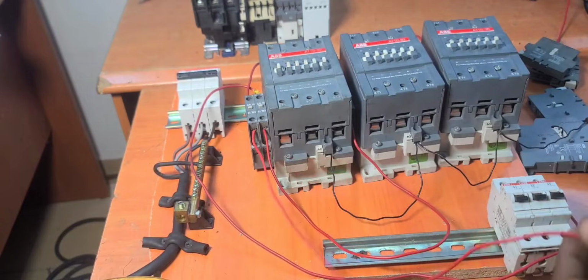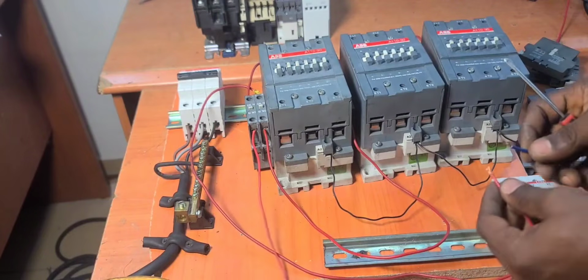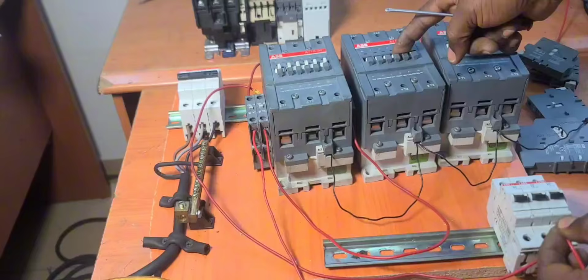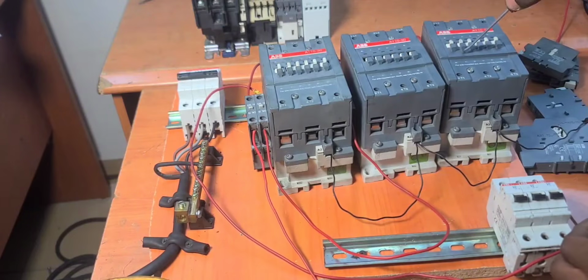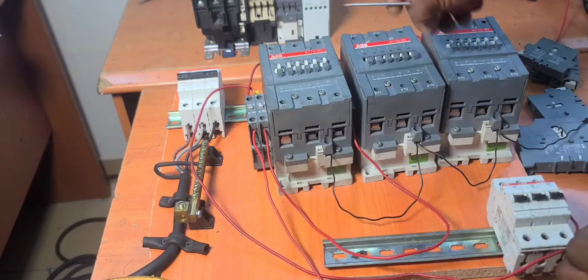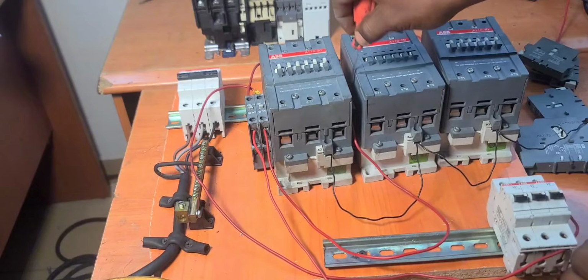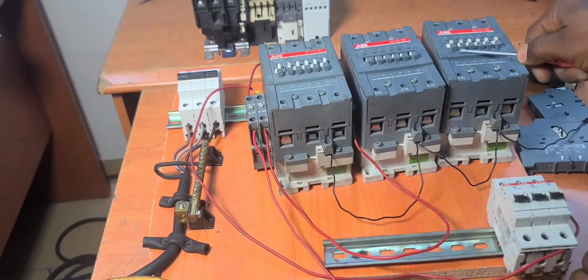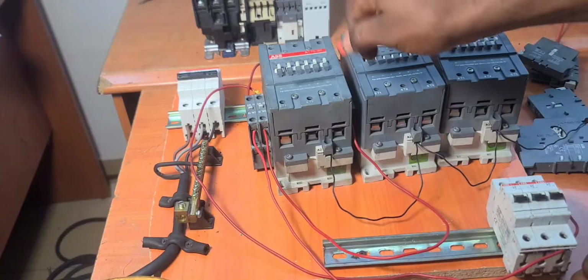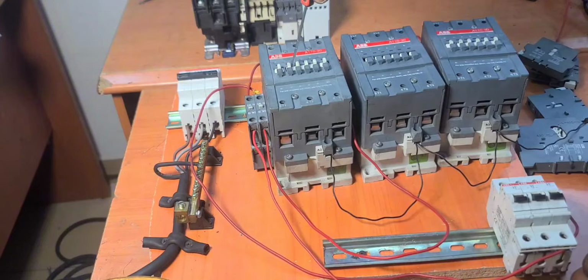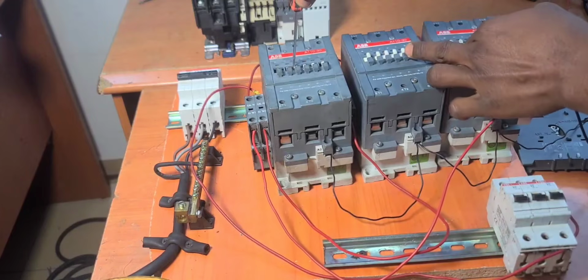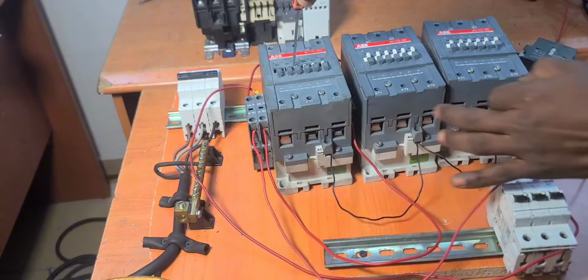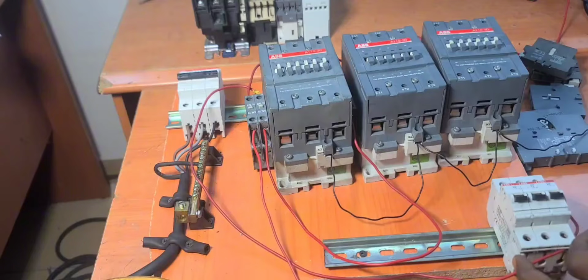So if we're going to test it, connect power to it. You see this one has depressed. So this particular one cannot close because this one is depressed. And this normally closed auxiliary that is here is open, meaning there is no way power can go to this one. Even if you start your generator, it cannot close. But if solar comes back up and this one goes down, this one will open, meaning the two sources of power can never collide. They can never connect together. All right? We'll leave it that way.